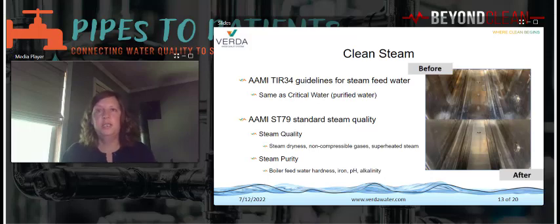So what should the SPS department do? AAMI TIR 34 is a guideline, a recommendation of best practices. It also has a standard, ST 79, that states the requirements for sterile processing. And one of those sections delves into steam quality and steam purity parameters that must be maintained. While the acceptable ranges are not defined here, water hardness, iron content, pH, and alkalinity are required to be monitored.